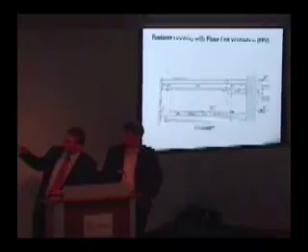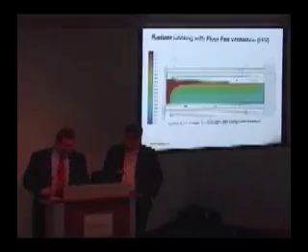Here's an image showing all this happening — air coming underneath the floor, being drawn through the cavity, back through the ceiling, and doubling up on systems. There is one duct back in the corridor. In the event of fire or smoke, the system can use that same duct — currently used to bring warm air back to the core — as the smoke exhaust, pulling smoke back to the ceiling rather than through the double skin.